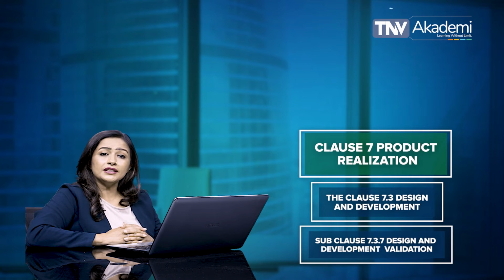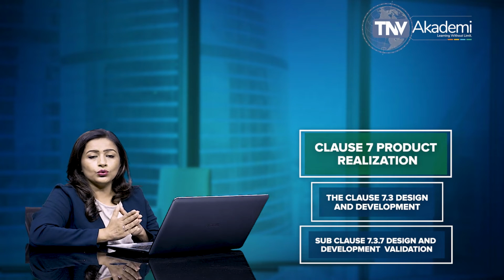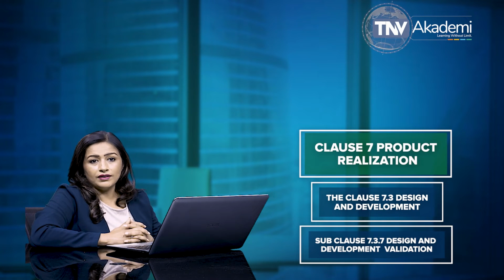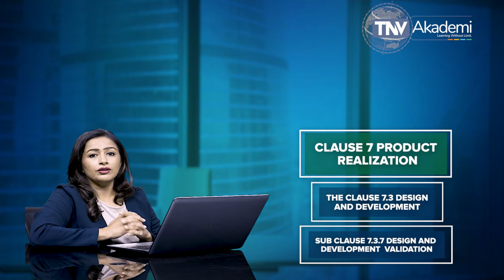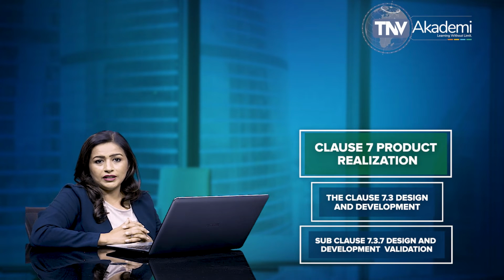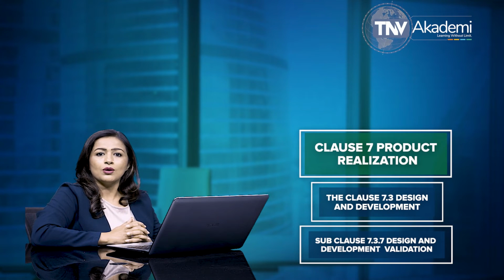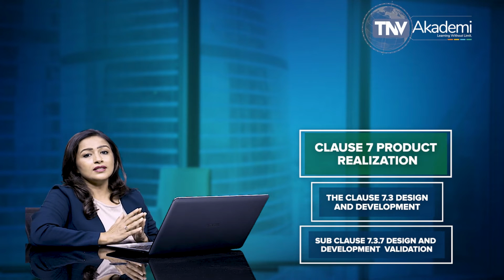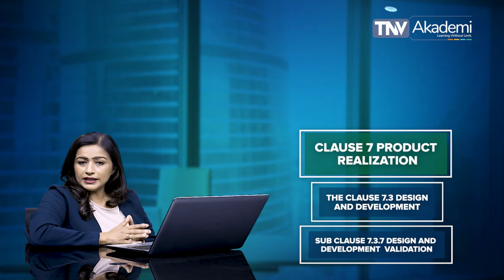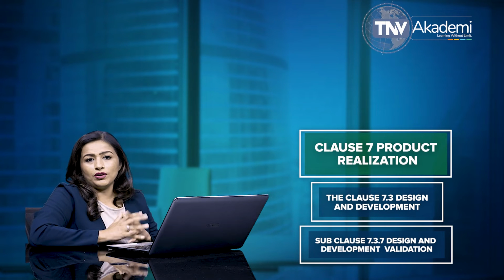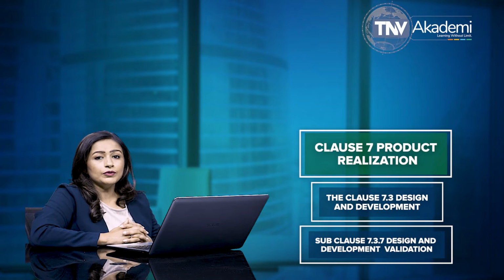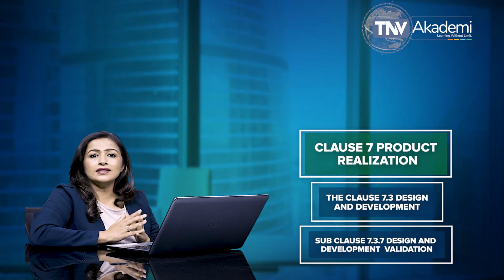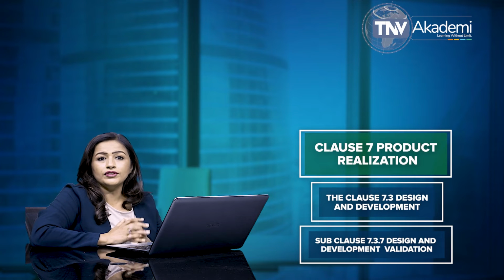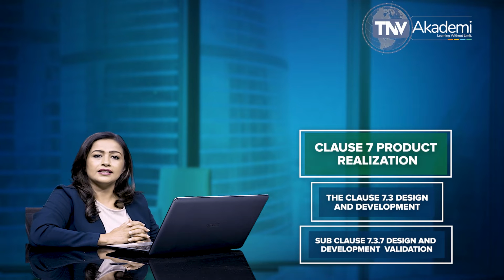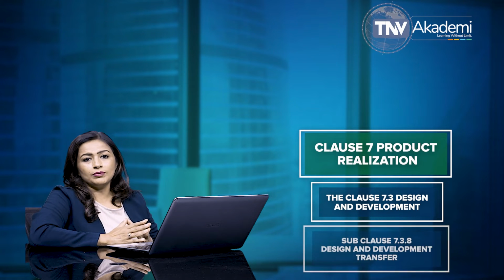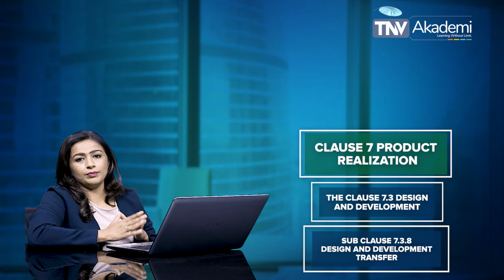If the intended use requires that the medical device be connected to or have an interface with other medical devices, validation is required to include confirmation that the requirements for the specified application or intended use have been met when so connected or interfaced. The clause states that validation is required to be completed prior to release for use of the product to the customer. Lastly, subclause 7.3.7 says that the organization is required to maintain the records of the results and conclusion of validation and necessary actions. Let's talk about subclause 7.3.8, Design and Development Transfer.